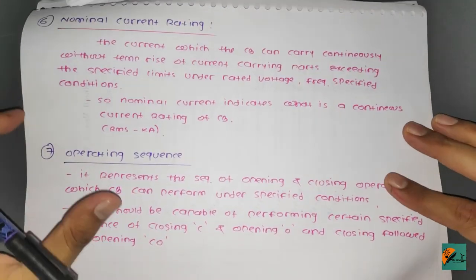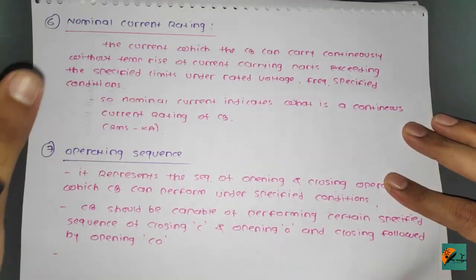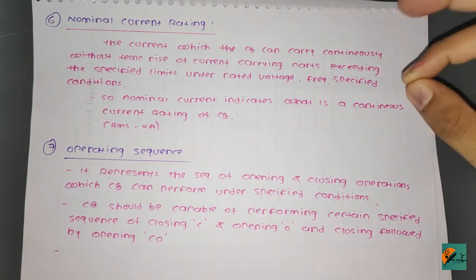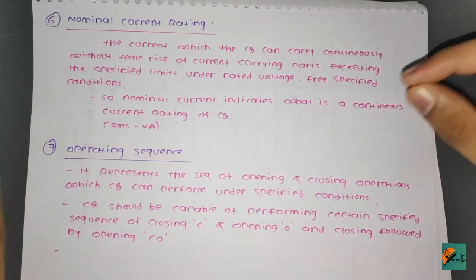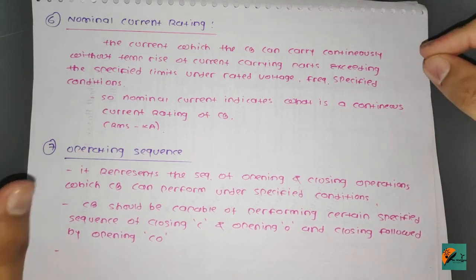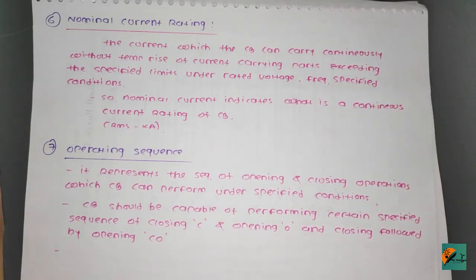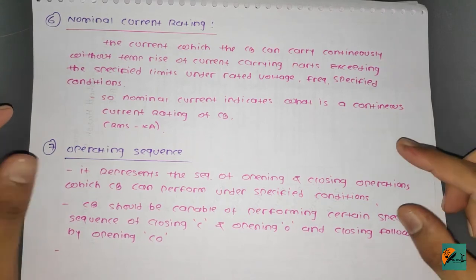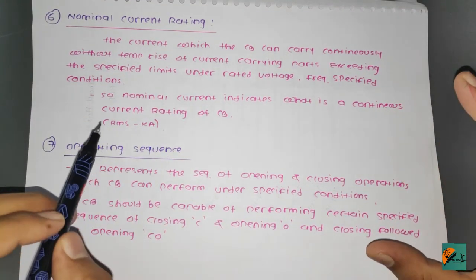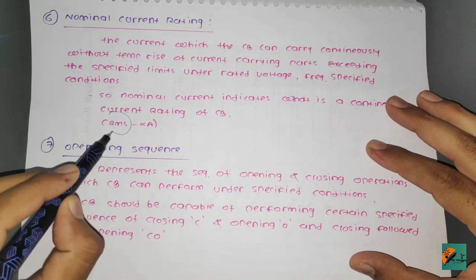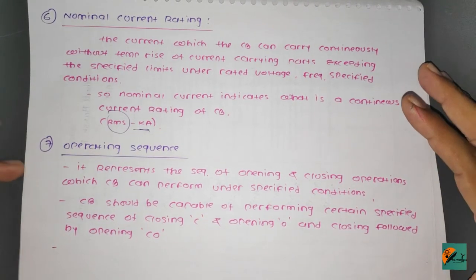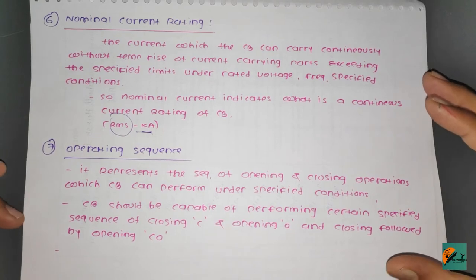The next one is nominal current rating. It is the current which the circuit breaker can carry continuously without the temperature rise of current-carrying parts exceeding specified limits, under rated voltage, frequency, and specified conditions. Nominal current indicates the continuous rating of the circuit breaker, expressed in RMS kiloamperes.